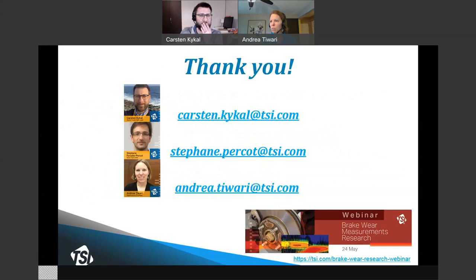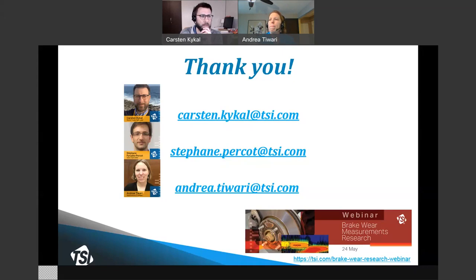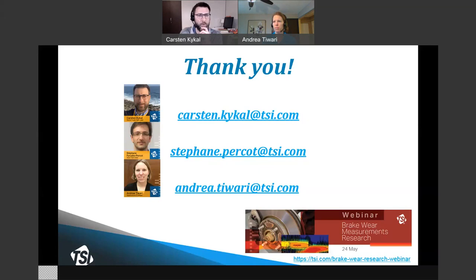I see one question asking for a copy of the slides — yes, the slides will be sent out to all registrants. There's a question about how CPCs are calibrated. Basically, a CPC is validated or calibrated against a system providing SI units — that would be an electrometer. You feed the setup with highly monodispersed aerosols of different sizes and compare the number concentration from the CPC under test to a reference CPC or reference electrometer or both. TSI offers all the solutions to build a complete test bench to do calibration on your own, or you can send your CPCs to TSI for calibration.